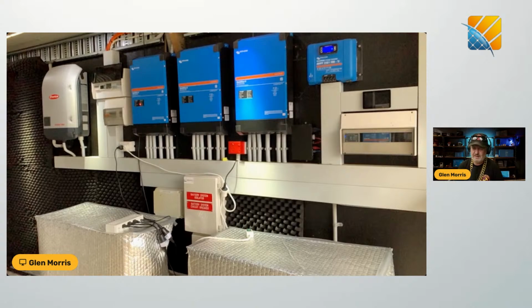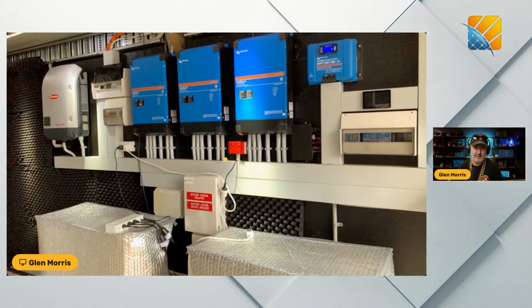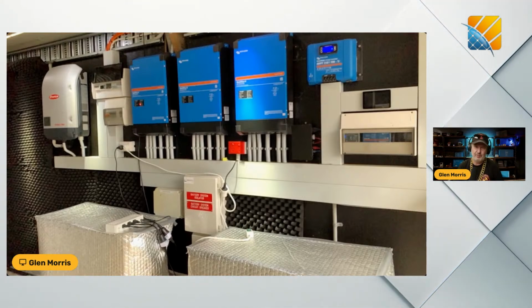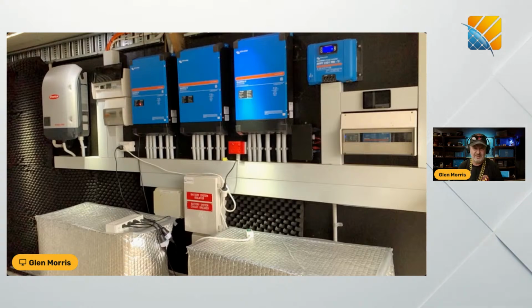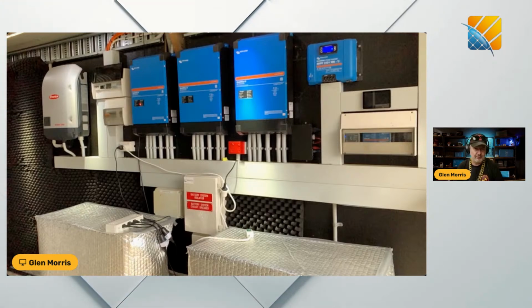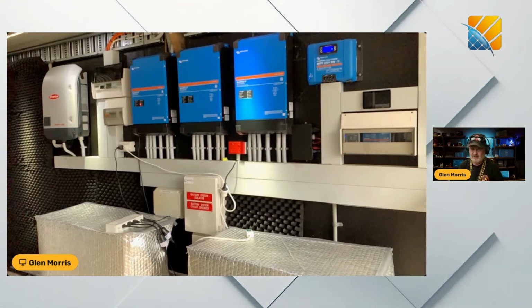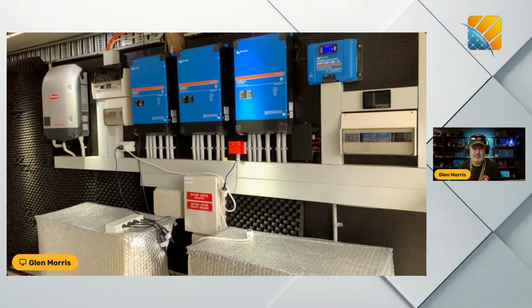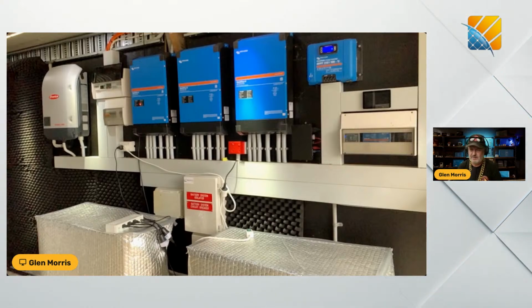Now, I didn't want to take the covers off because it was just too much work and it's freezing cold at the moment, and they actually like to be kept warm. So we're at 5 degrees here. These batteries work best above 15 degrees Celsius internally, so we keep them a little toastier with these wraps. But normally they come with an outdoor enclosure, which we didn't have. We just had the bare battery module. So the outdoor enclosure would provide some of that protection.